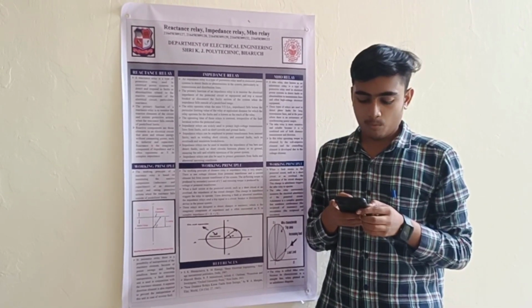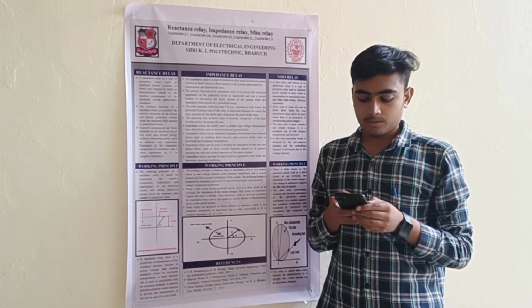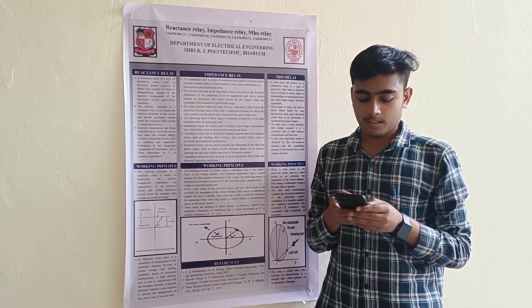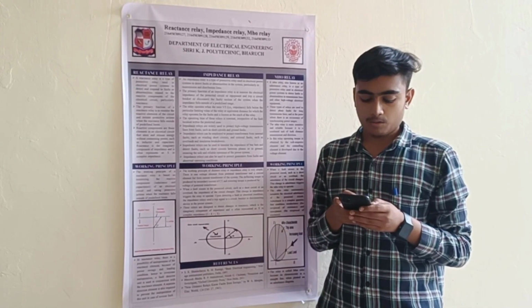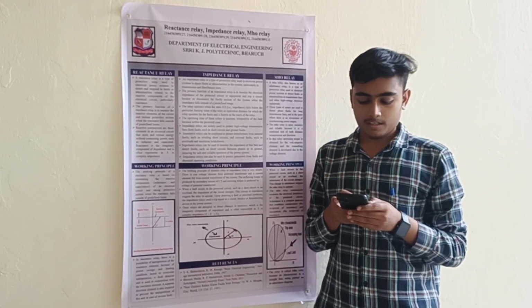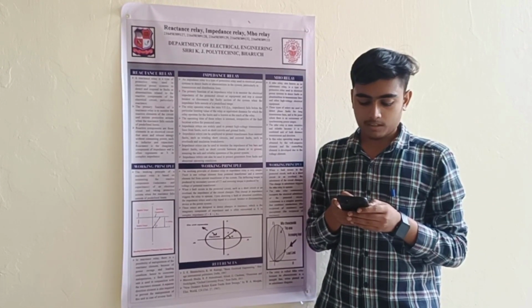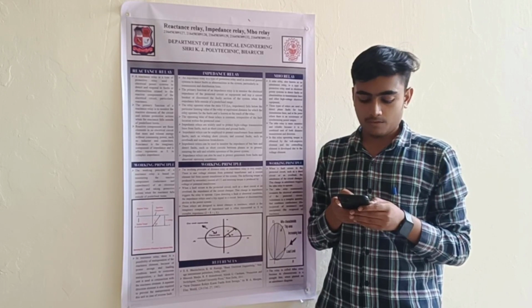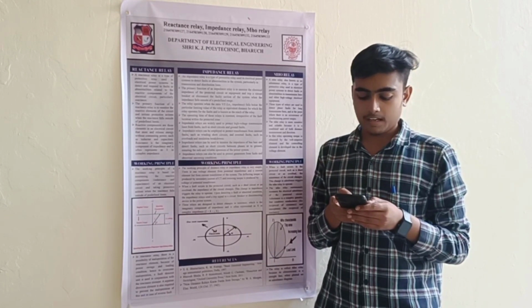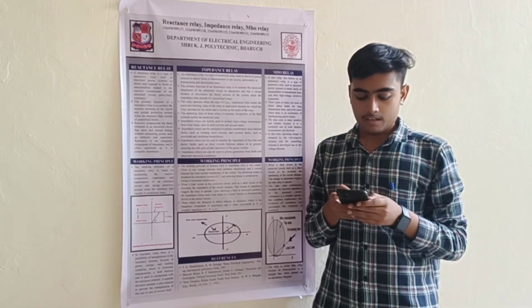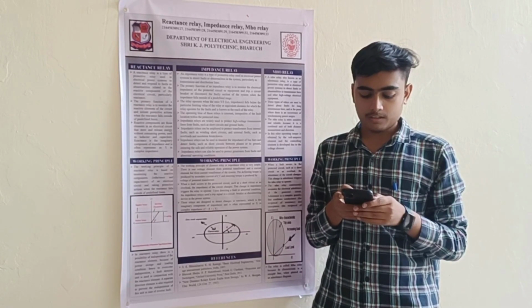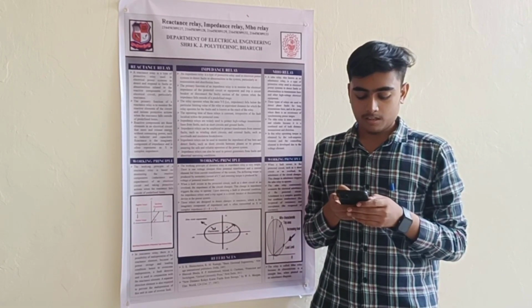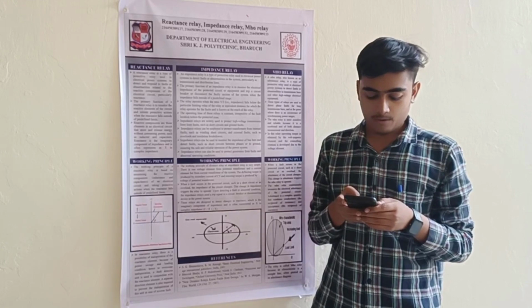Backup protection. Mho relays can be used as backup protection in conjunction with other types of relays, such as overcurrent relays. If the primary protection fails to detect a fault, the Mho relay can act as a backup and initiate the tripping of the circuit breaker to isolate the faulted section.